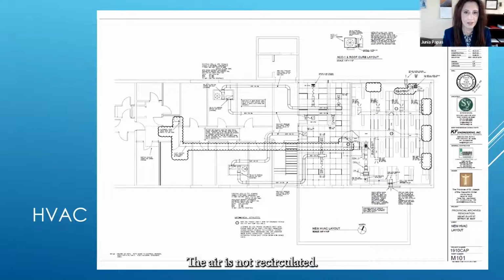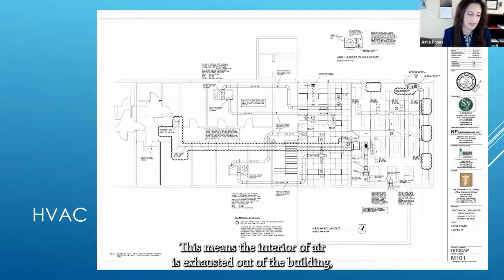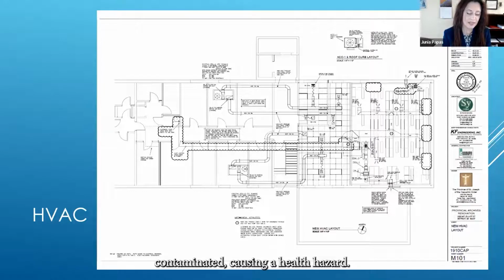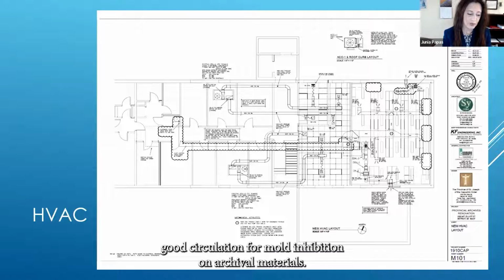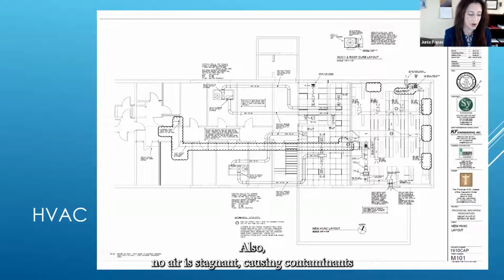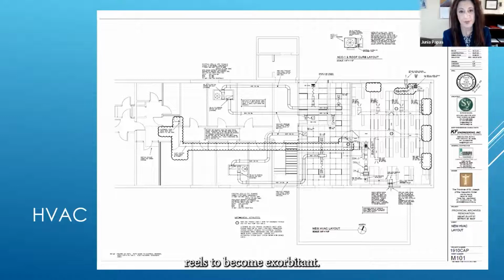The air is not recirculated. This means the interior vault air is exhausted out of the building and fresh outdoor air is vented into the building. This is common in hospitals where air can be contaminated, causing a health hazard. In our case, this air exchange system provides good circulation for mold inhibition on archival materials. Also, no air is stagnant, causing contaminants such as cellulose nitrate gas from nitrate film reels to become exorbitant.